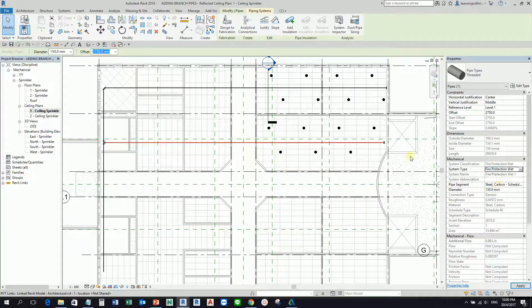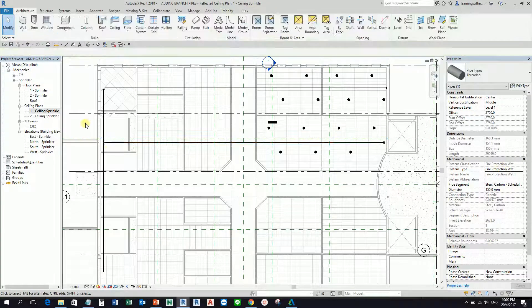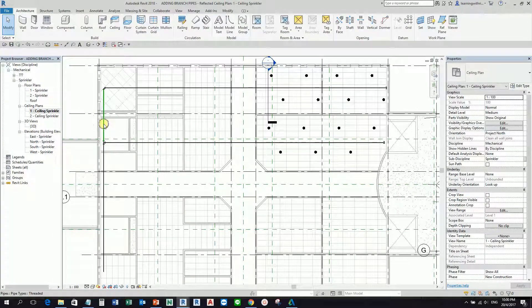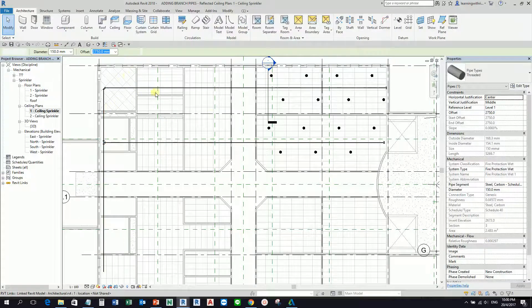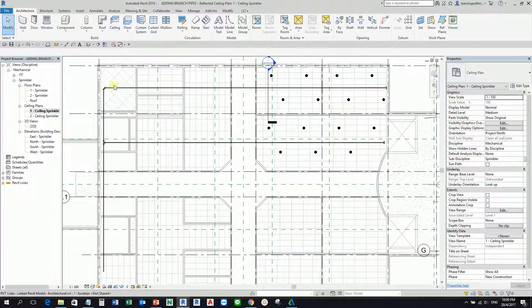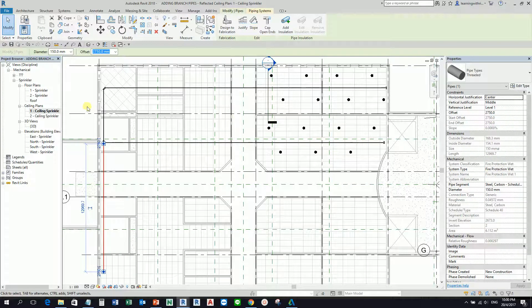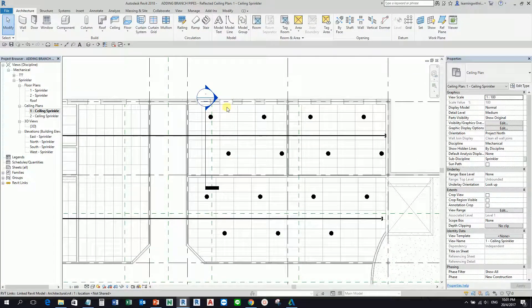You'll notice the type is now 'Fire Protection Wet.' If I select another connected pipe, it will also change to 'Fire Protection Wet' — no need to change them one by one. As long as they are properly connected, the system type will propagate to all connected pipes.